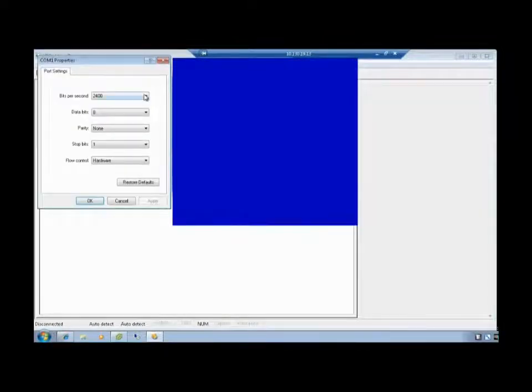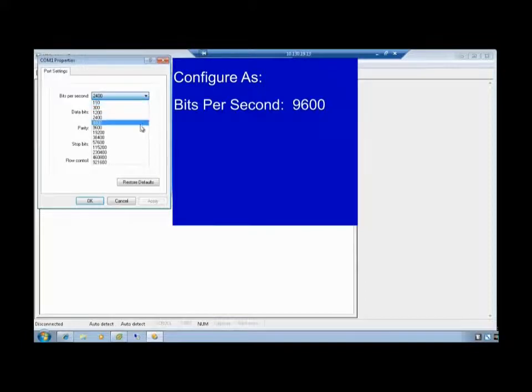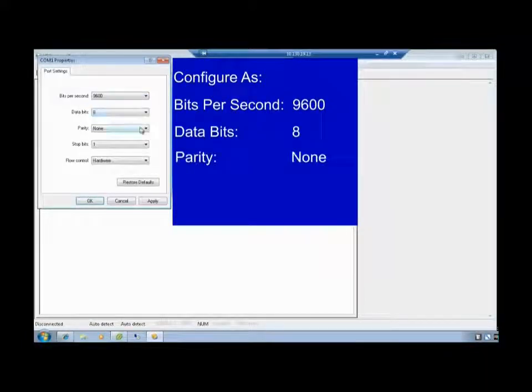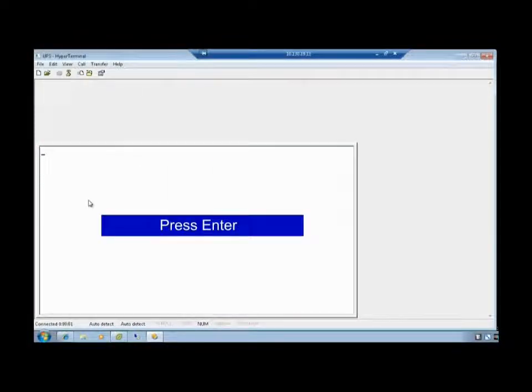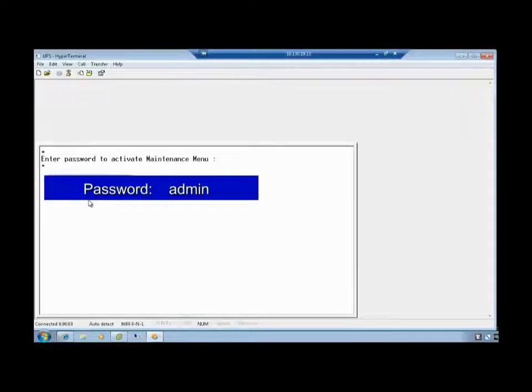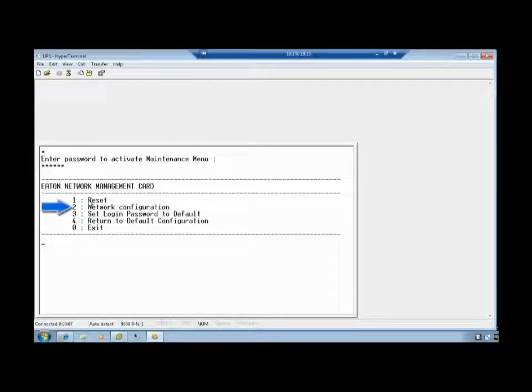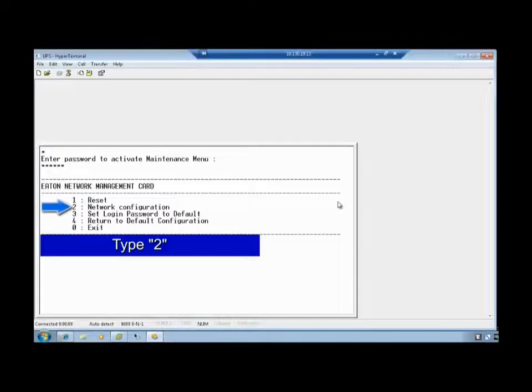Select the COM port properties. Configure as bits per second 9600, data bits 8, parity none, stop bits 1. Flow control, none. Select OK. Once the screen opens, press Enter to proceed. Activate the maintenance menu by entering the password of admin in all lowercase. Press Enter. Choose option 2 for network configuration by typing the number 2.